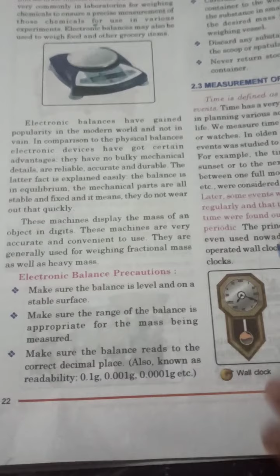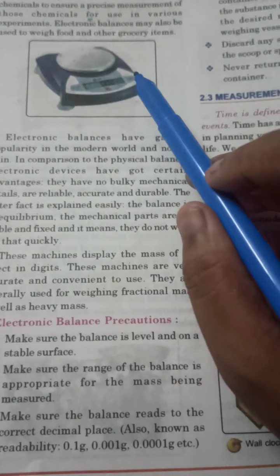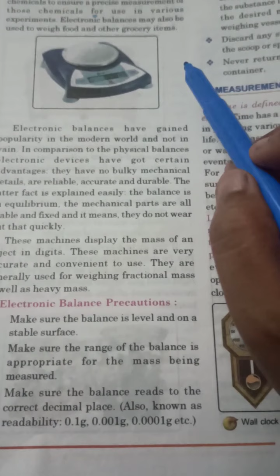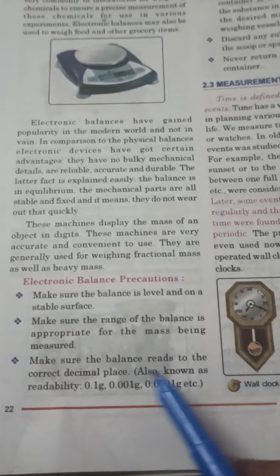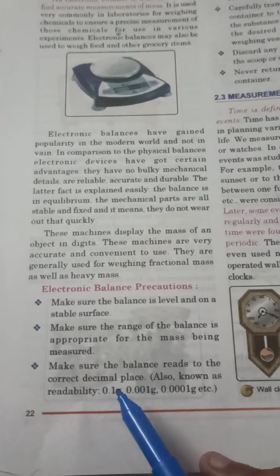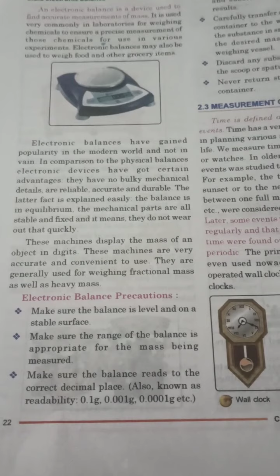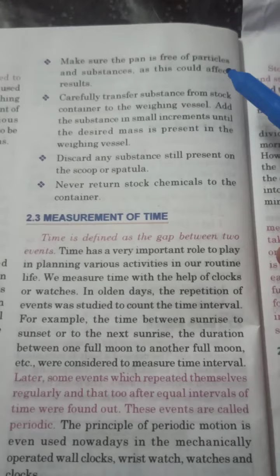Make sure the range of the balance is appropriate for the mass being measured, because here we can see a button given, so we can change the settings or change the units from that button. Make sure the balance reads to the correct decimal place, also known as readability: 0.1 gram, 0.01 gram, and 0.001 gram. Whatever weight we are measuring, the balance should be at the correct decimal place. Now make sure the pan is free of particles and substances, as this could affect results.